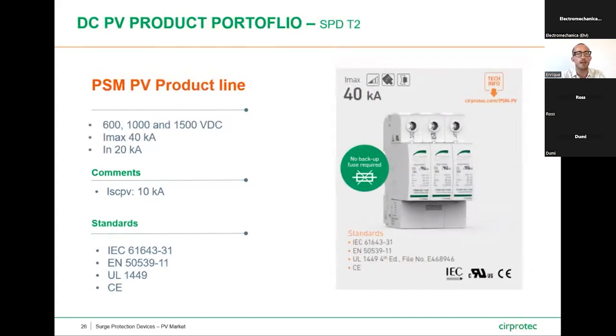And the second top runner DC SPD product line we are manufacturing is the SPD type 2 product range. It's named as PSM PV product line in Cirprotec. We have solutions for 600 volts DC, for 1000 volts DC, and for 1500 volts DC. It's declaring an Imax 40 kA and an In 20 kA. Those are the parameters belonging to the type 2 SPDs. Then the same as our type 1+2 DC product range, it's tested and we are declaring an Iscpv of 10 kA. The same, it's manufactured under the IEC and the EN standards, is UL certified, and is CE marked.